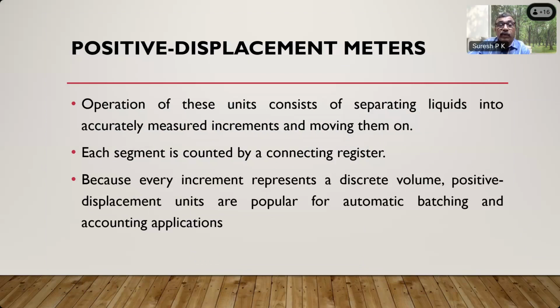Then positive displacement flow meters. Operation of these units consists of separating liquids into accurately measured increments and moving on. Each segment is counted by the flow meter, which will segregate a particular amount of fluid within its chamber and then release it to the downstream. Collect it from the upstream, collect it in the chamber, release it to the downstream. The number of rotations of these chambers will give you the accurate volume of what is total volume.